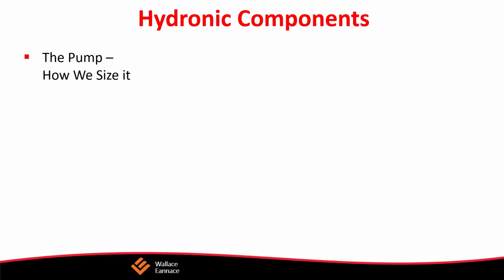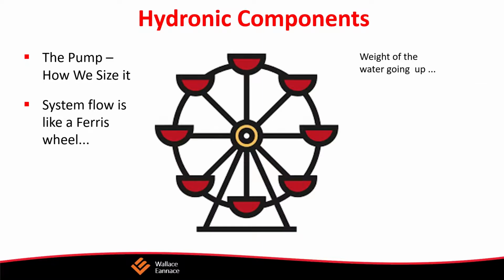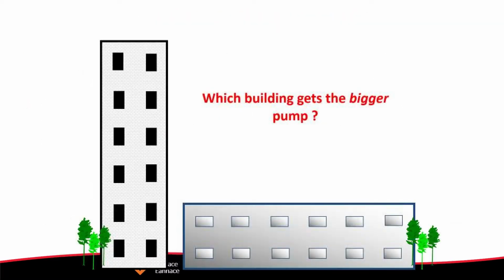Do I need a fancy flow meter to determine flow? No. All you need is a pressure gauge and a pump curve. A pump curve is a chart provided by the pump manufacturer. This chart shows feet of head on one side and gallons per minute on the other. In the middle of the chart, you'll see one or more curves. These curves represent the impeller size of the circulator. Some charts will have multiple sizes shown on a single chart. Some charts will only have one curve.